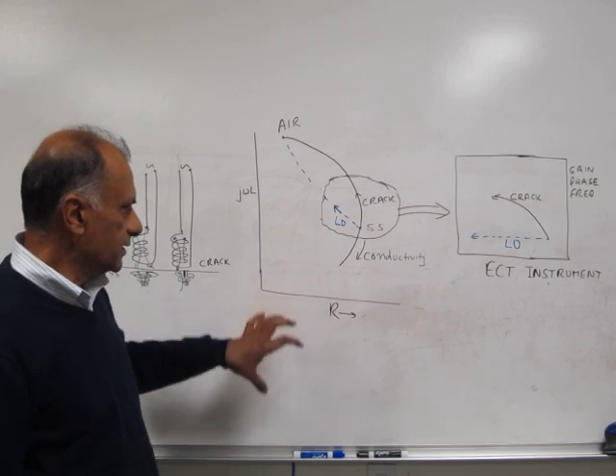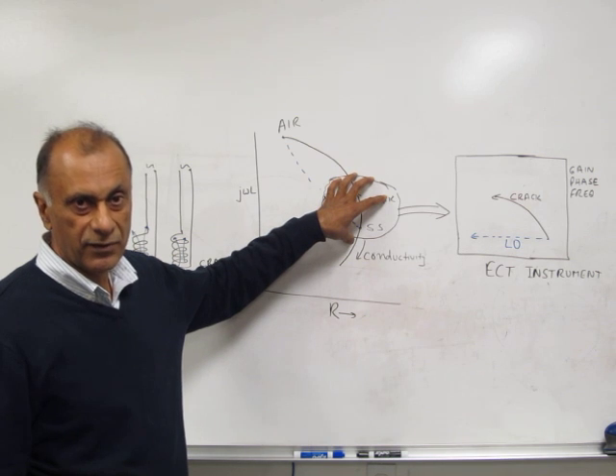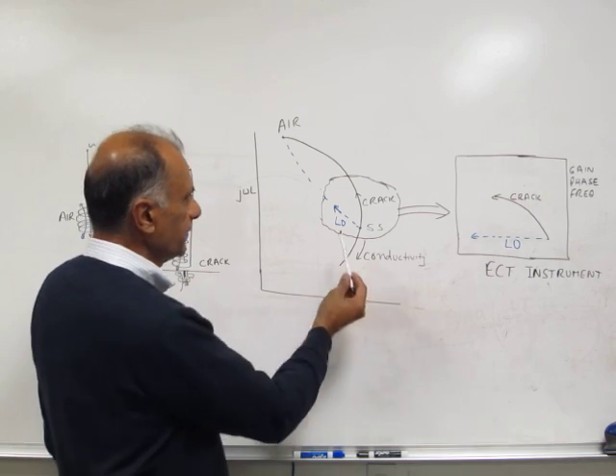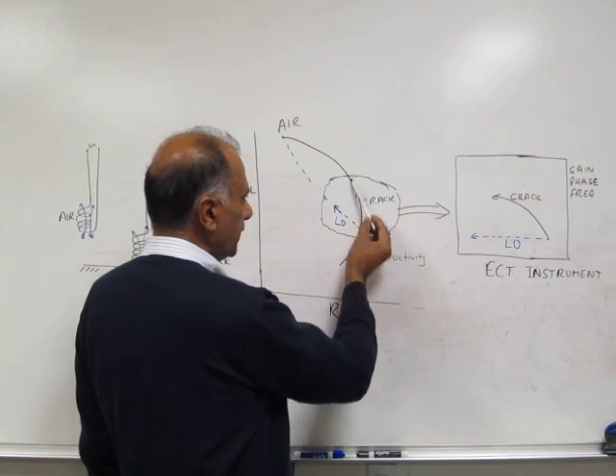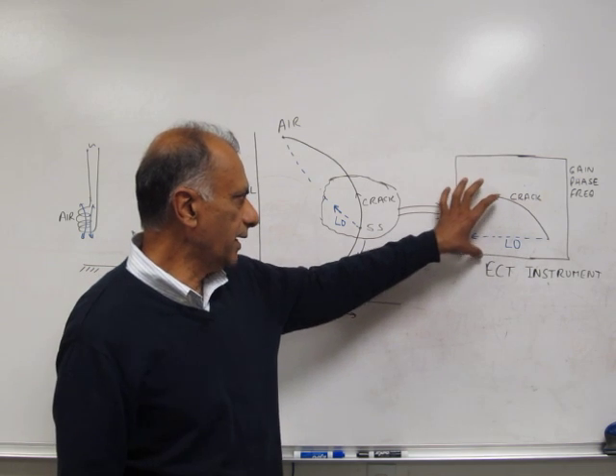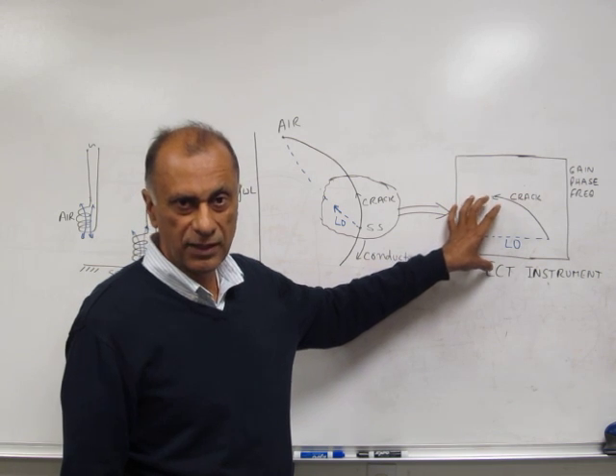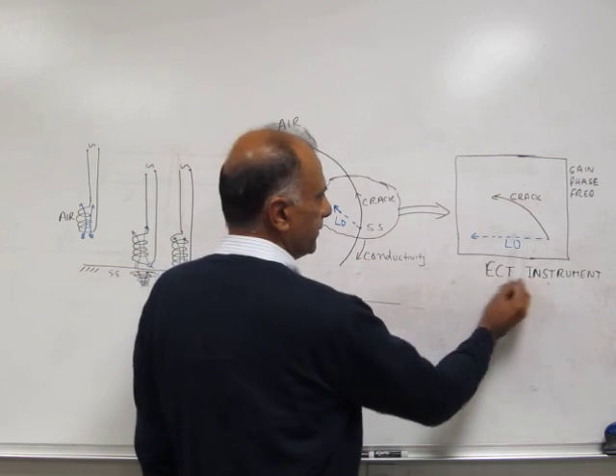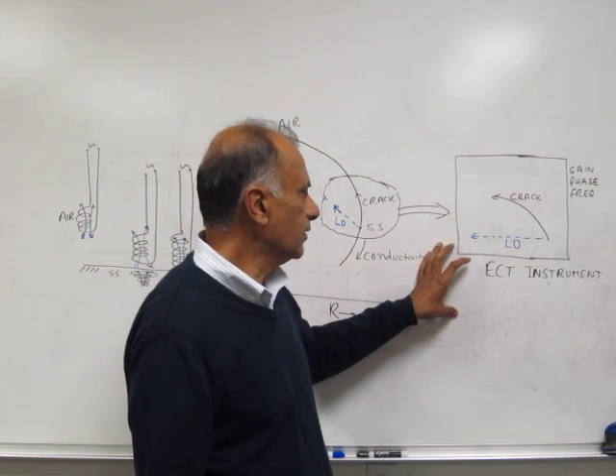For eddy current testing, we take the small display and transfer it to the eddy current instrument display shown in this figure. The lift-off line is here and the crack line is here. We change the phase angle on the machine to bring the lift-off angle to zero degrees, and when that's done, the crack signal is displayed accordingly.